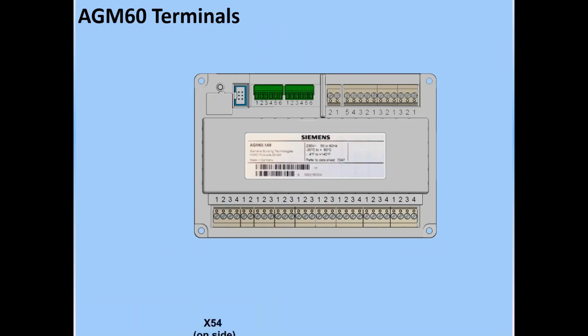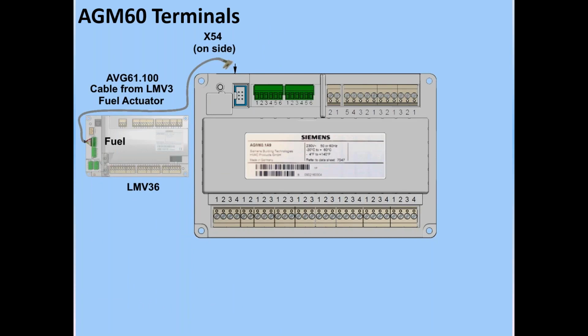On the AGM60, we have a terminal on the side, X54, and it can take that cable, that AVG, from the fuel connection on the LMV336, the dual fuel. So an AGM60 is used whenever we're using dual fuels. You would plug that in from the fuel on the LMV3 to the side terminal on the AGM60. Then on the AGM60, you can connect up 2 different fuel terminals, one for fuel 0, one for fuel 1. And then the AGM will automatically switch SQM33 actuators depending on what fuel you're on.